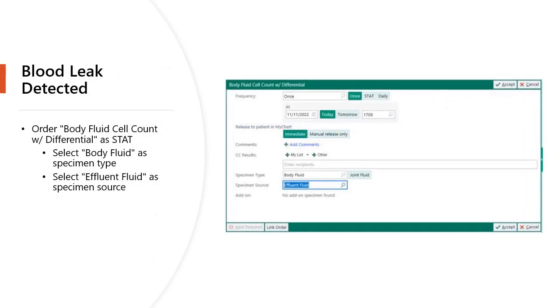Blood leak detected has not changed this year, but just as a reminder, the order is fairly new. And that can be obtained by aspirating a sample out of the yellow port on the CRRT circuit with a 21 gauge needle or smaller. Basically, that's any needle size besides blunt tips. And the order that's placed for the lab is body fluid cell count with differential. Make that stat, and the specimen source should be effluent fluid.